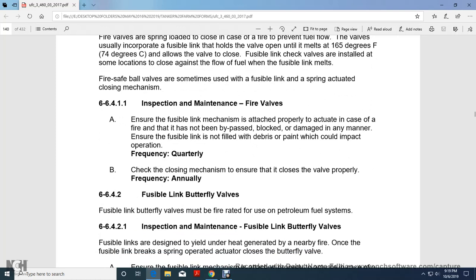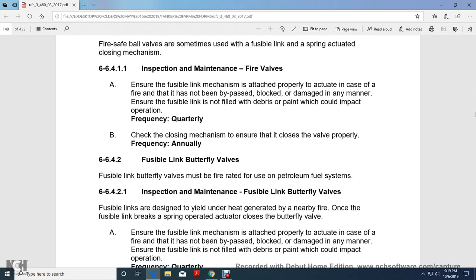6411 Inspection and maintenance of fire valves. Ensure fusible link mechanisms are attached properly to actuate in case of a fire and have not been bypassed, blocked, or damaged in any manner. Ensure fusible links are not filled with debris or paint which could impact the operation, quarterly. Check the closing of the mechanisms. Ensure the valve closes properly.